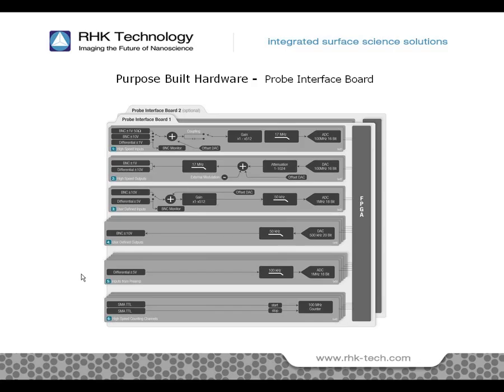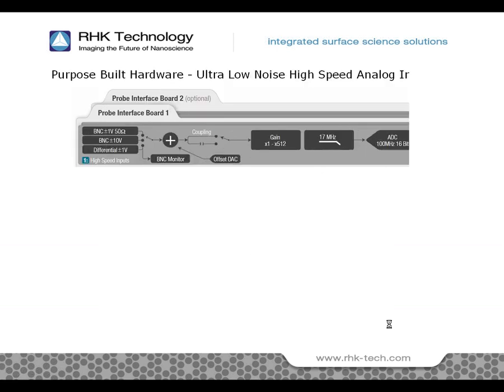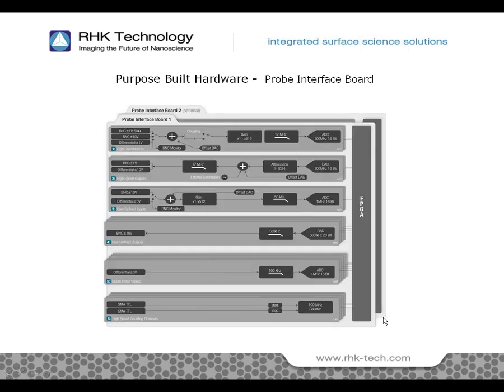The probe interface board set that is shown contains most of the ADCs and DACs that interface to the microscope. These ADCs and DACs are all directly connected to a very large-scale FPGA chip that handles most of the functions of the controller. Many people are familiar with DSP technology, which was common in previous generation controllers. Where a DSP could handle a string of tasks at a high speed, they were serial devices and could only handle one calculation at a time. FPGA technology, on the other hand, is inherently parallel, so they can process many tasks simultaneously. FPGA has largely replaced DSP technology in advanced instruments.